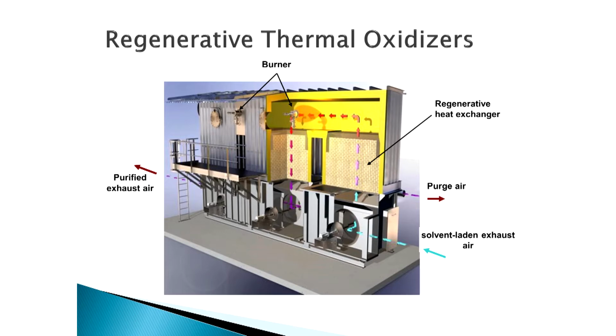We get complete combustion in the combustion chamber, so the real inefficiency of these systems is in the valves and in the inlet and outlet plenums. And that's why if we want to get higher destruction efficiency, we want to get 99%. In the past, there's been a 3rd tower, and that 3rd tower is offline, and we purge the unburned hydrocarbons in that plenum back into the combustion chamber for a second pass at combustion, if you will. And that's how we're able to get very high efficiencies there. In the field, you may see 3 towers, you may see 5 towers, you may see 7-tower RTOs that could be sized for as high as 250 to 300,000 SCFM.